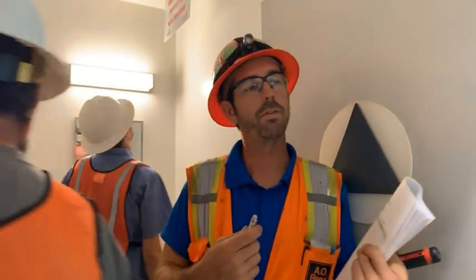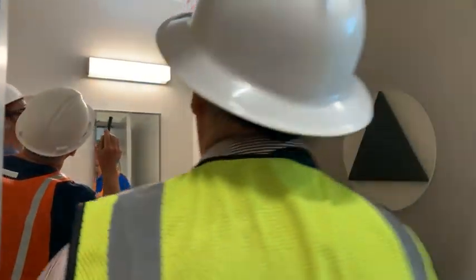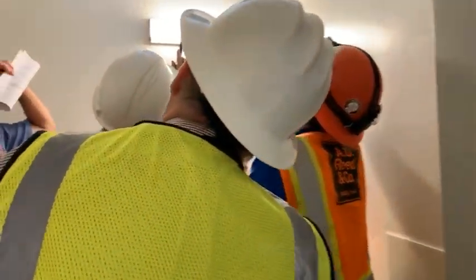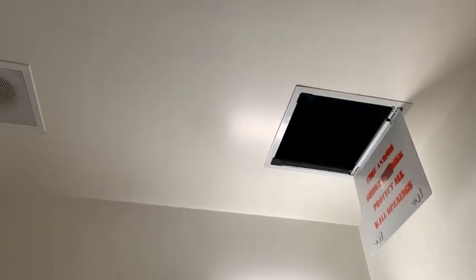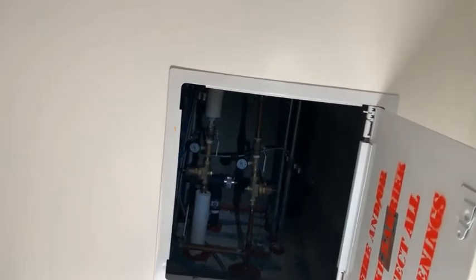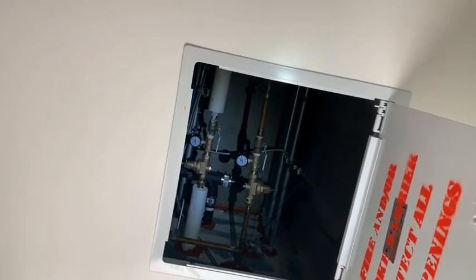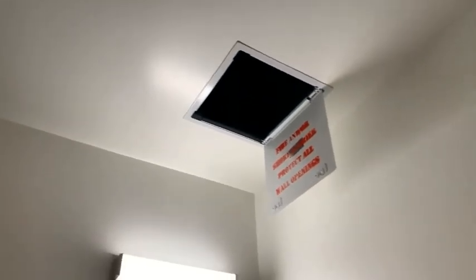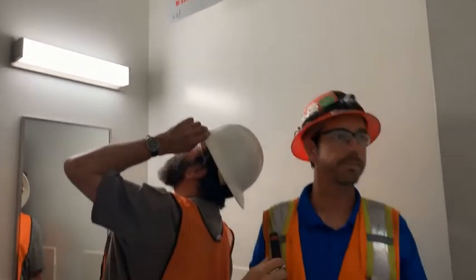Remember I was talking about the pressure reducing valves? Because we're at 80 pounds on that main regulator and we're going up 8 floors, we have zone pressure reducing valves. That's going to be up here. Okay, so you have one for the hot on the left and one for cold on the right. So they bring it from 80 to 45. The outlet pressure on all the pressure reducing valves on floors 1, 2, and 3 will be 45 psi.